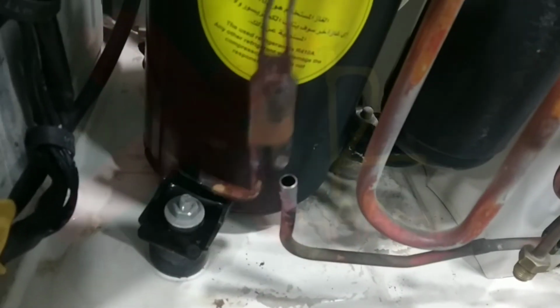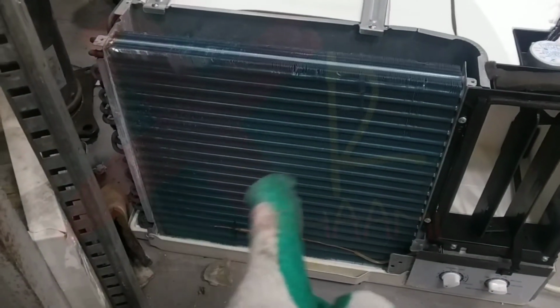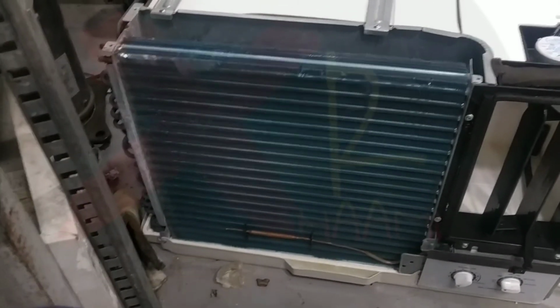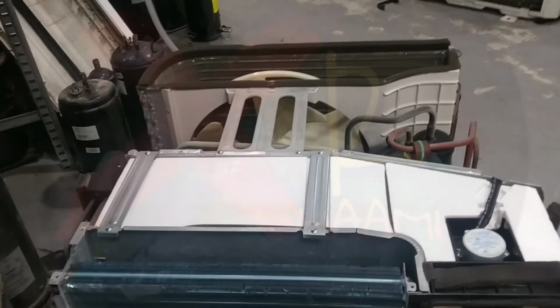Sometimes the refrigerant does not circulate well in these pipes, as you can see, because of a choking problem. This is the filter, or you can say dryer. Most of the time this filter is choked with oil, because the compressor has oil inside. So most of the time we face this problem. Sometimes the oil comes inside the tubes and chokes the filter or dryer, so the refrigerant does not circulate well. This is also a cause of icing over.